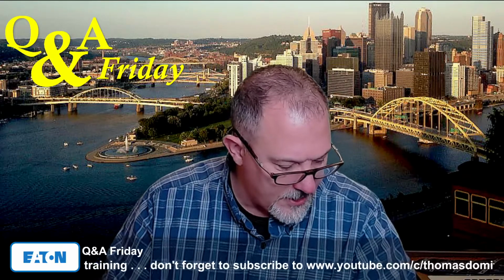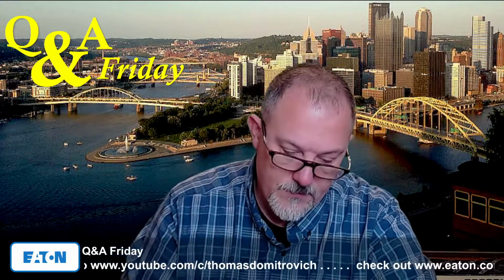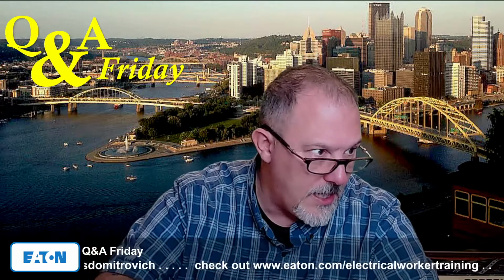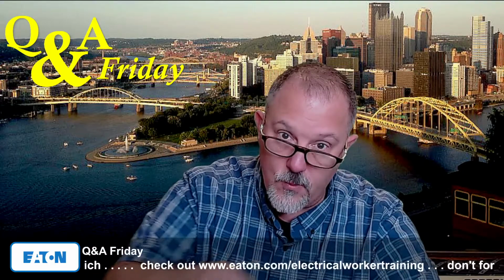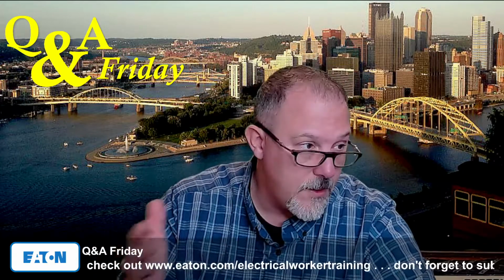I should know this section off the top of my head, and I should not be digging. 230.82. Only the following equipment shall be permitted to be connected on the supply side of the service disconnecting means. So you would think that what is in the standard will align with what is in the code.